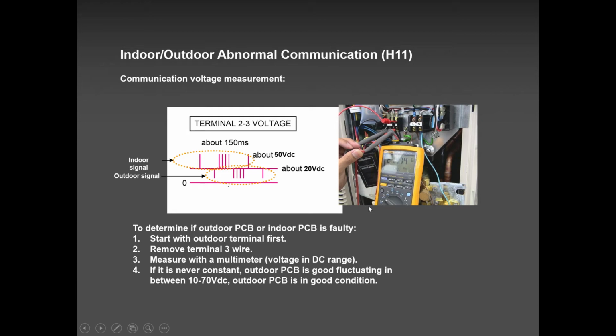You remember I spoke about the multimeter? That's the meter you need to use, guys. Don't use an amp probe. It will give you sometimes wrong readings and you may condemn the board. Meanwhile, the board is in good shape. It's the meter. So anyway, use that multimeter, measure between number 2 and number 3. Leave the number 3 wire that goes to the indoor unit hanging. If you get a communication of up and down DC voltage, anywhere from 10 to 70, 10 to 40, 10 to 50, 50 back to 10, up and down, up and down, your outdoor unit board is good. Your outdoor unit PCB is good. You have a problem with the indoor PCB.